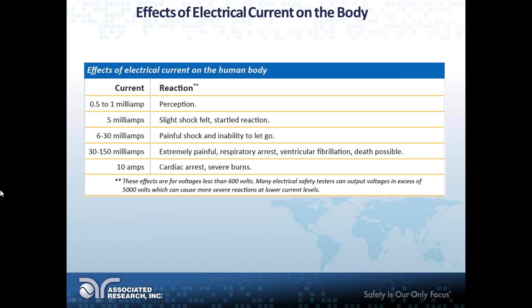Now, talking about the effects of current on the human body, I have a general table here. This can vary depending on various factors — the environment and conditions you're in, as I explained previously. One thing to keep in mind: these effects are listed for voltages less than about 600 volts. Many electrical safety testers can output in excess of 5,000 volts, which causes much more severe reactions at lower current levels than listed here, so take that into account when using an electrical safety tester.